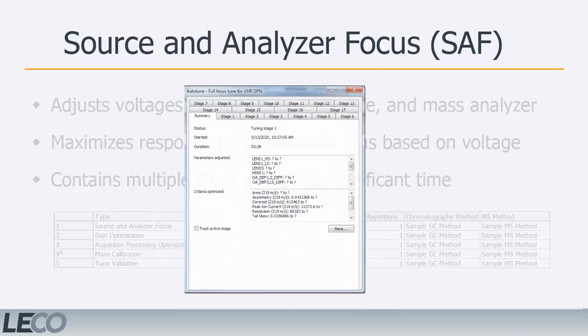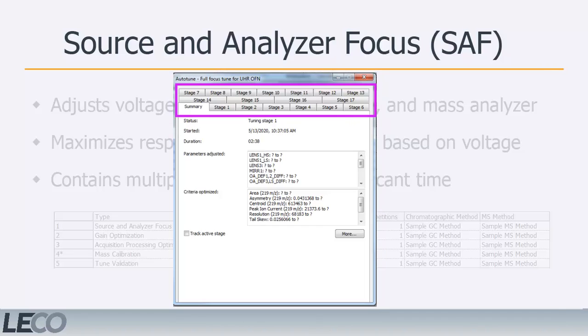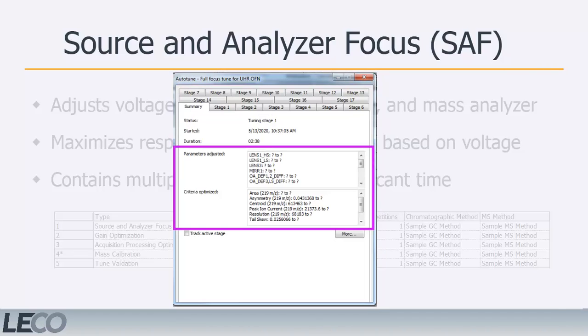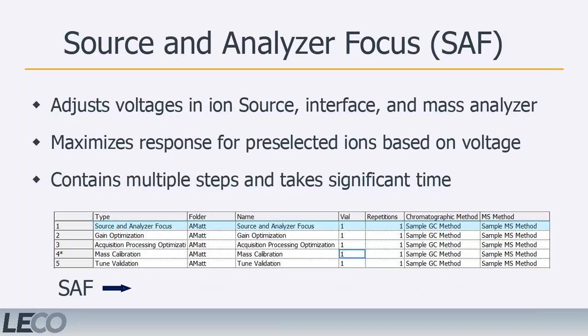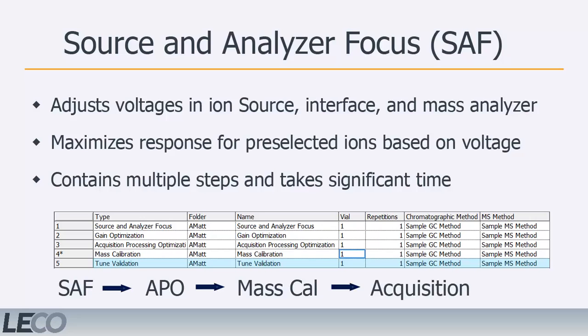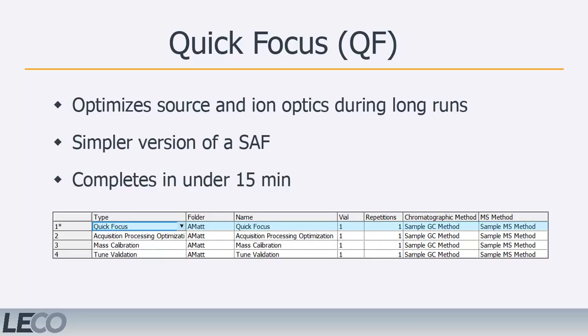When the SAF begins, a window is generated displaying the various stages of optimization with a description of which elements are being adjusted during each stage of optimization. Once the SAF has finished, the acquisition processing optimization and mass calibration steps must be run before continuing to sample acquisition. A quick focus can be periodically performed during prolonged data acquisition runs in order to keep the source and ion optics at optimum performance and counteract any gradual drifts.